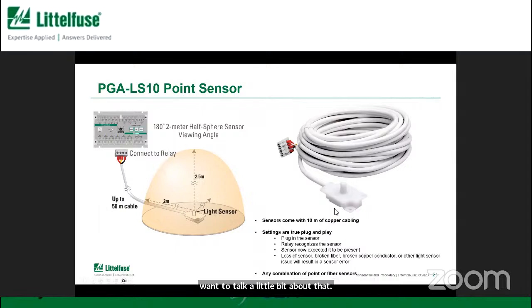These light sensors are installed inside the cabinets, and they look for the light that comes from the arc that starts to burn. One sensor has a pretty good window. You don't have to get super close. You don't have to be 2 centimeters away from the arc. These sensors can see 2 or 2.5 meters for a relatively small arc. So if you think about one piece of equipment, you could have a light sensor in the ceiling on the top of the enclosure, and it could see an arc all the way down to the bottom. This is a single point sensor that you install in one location, and it can see, in this hemisphere, like I said, about 2 to 2.5 meters.